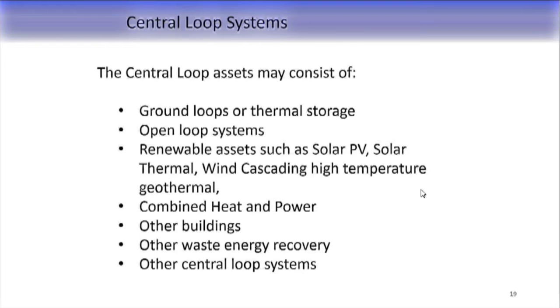When we start talking about combined heat and power, what's the major problem? I have to have a dedicated building or dedicated spot to take the heat. What happens if in the wintertime I'm able to bleed it into the central loop, which will raise my circulating temperature and increase the efficiency of the heat pumps all the way across campus. Now I've taken an asset supplying 1 megawatt, the CHP, and I'm multiplying its effect. I don't have to have steam, I don't have to have a hospital.